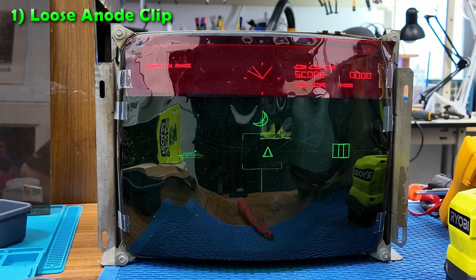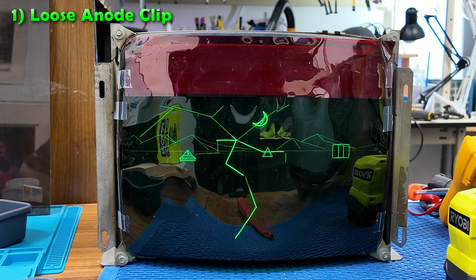The first thing I noticed when we got the monitor out was that the anode clip going into the monitor was not very secure - we could see it was partially out of the monitor tube. So we fixed that, and we got what appeared to be a slight improvement in the brightness, but it wasn't a fix to the problem.